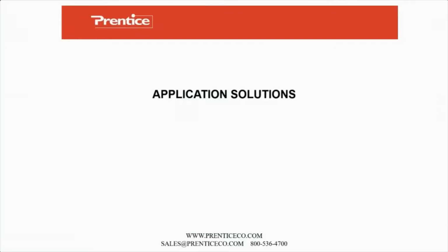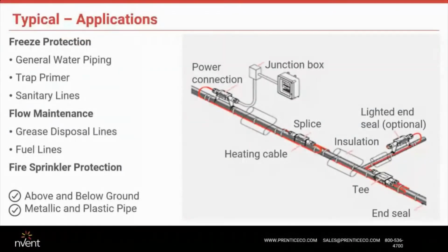All right, so let's get right into application solutions. As I said in series number 1, we talked a lot about heat trace that we put on the pipe. Those applications you guys might see out in the field most commonly are, of course, keeping pipes from freezing. A lot of areas that people don't think about when it comes to freezing are valves or low spots like traps. Another one is whenever you're taking pressure and regulating it down, whether it's gas or air or whatever it is, when you condense gases, it does tend to have a much higher capability of freezing. So that's another application you guys might see out in the field.